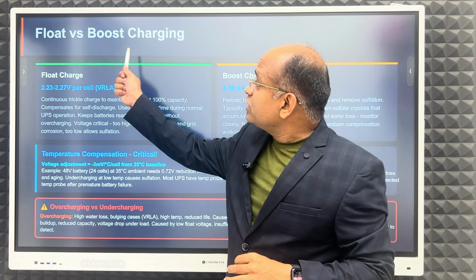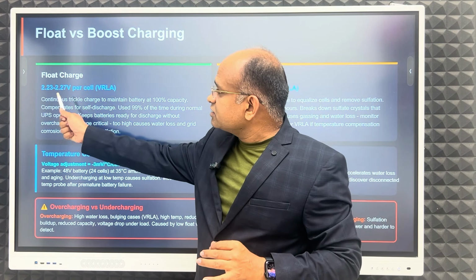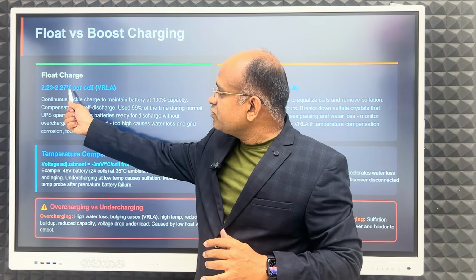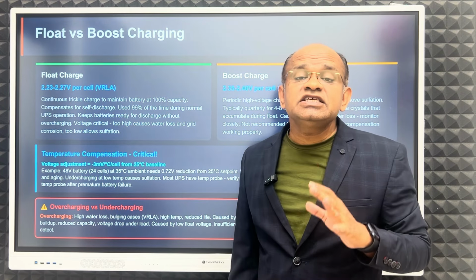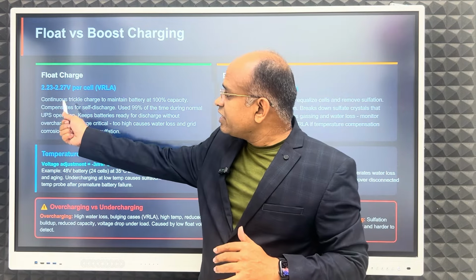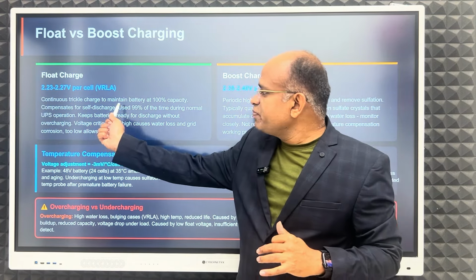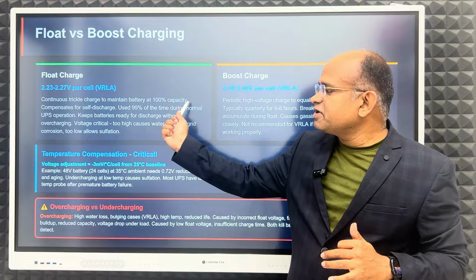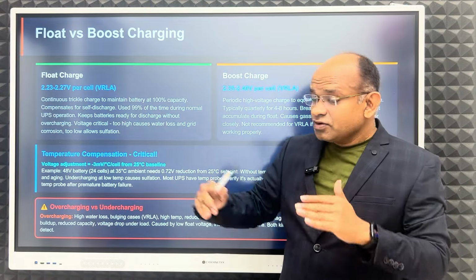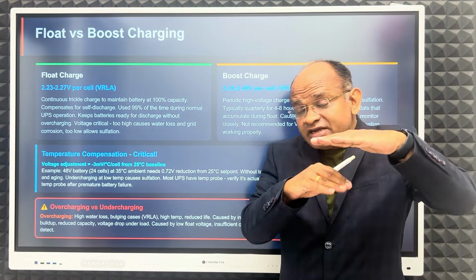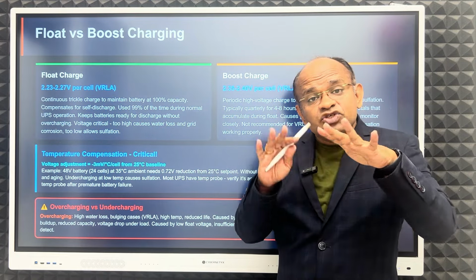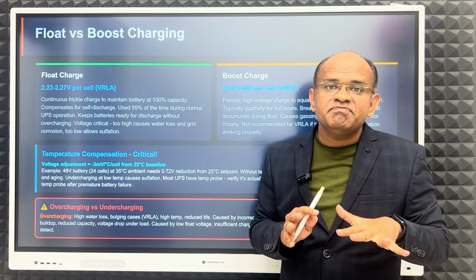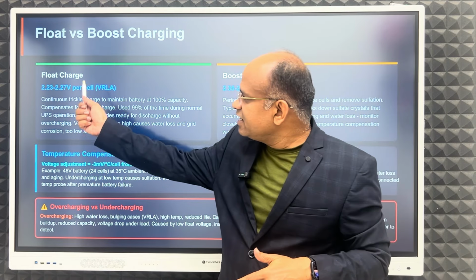Now, float versus boost charging. Float charge is 2.23 to 2.27 volt per cell. This is float charge. It is a continuous trickle charge to maintain the battery at 100% capacity. Why are we keeping it floated? Because it should be 100% charged all the time, at maximum capacity. That is why it is floated.